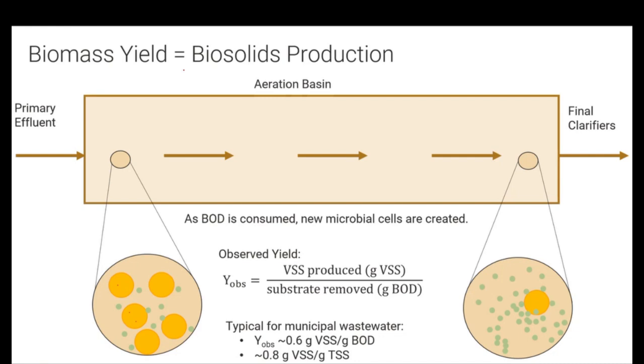And the yield is typically based on your influent food. So the yield we talk about is how much VSS we produce. We consider our bugs VSS. Basically, how many pounds of this do we produce per pound of BOD coming in? This gram can be changed to pound. It's gram per gram or pound per pound, whatever unit you want to use. But Jonathan, the typical number is around 0.6, and you can calculate it for your own plant. So it's 0.6 for VSS.